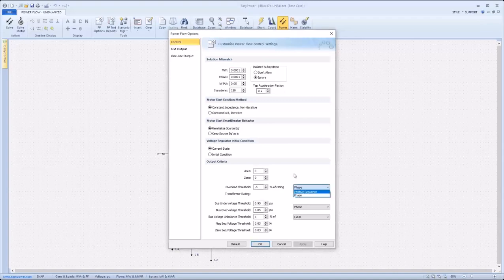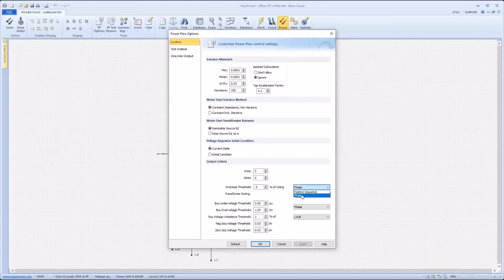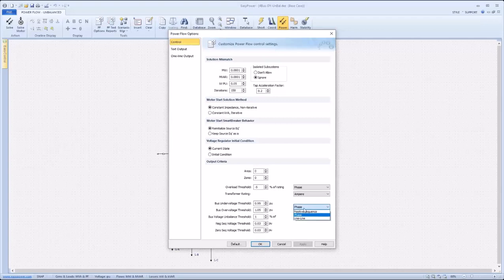Positive sequence uses only positive sequence values to make the comparison, where phase uses the individual phases to compare to one another. Bus undervoltage and overvoltage thresholds can also be specified with these similar options, positive sequence and phase, as well as the addition of the line-to-line option.